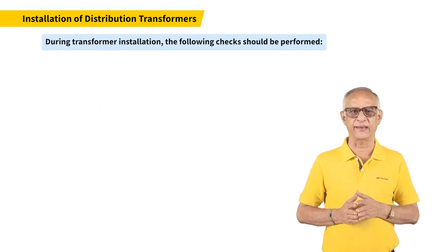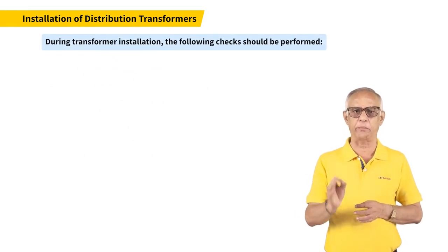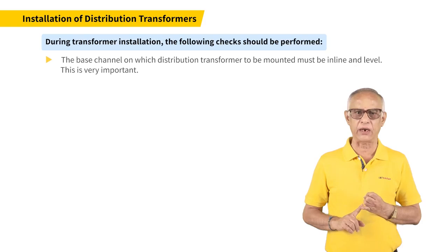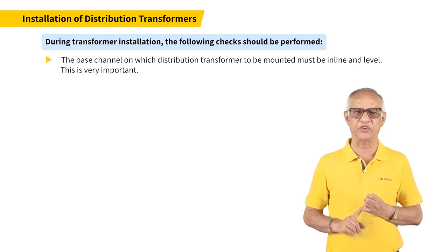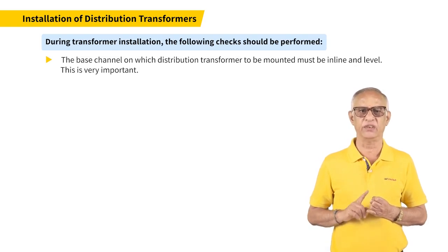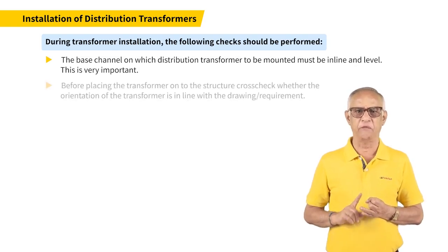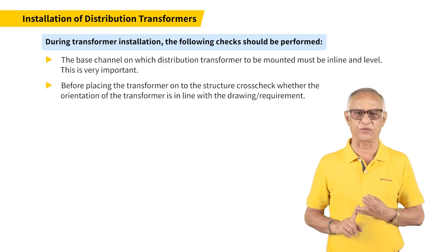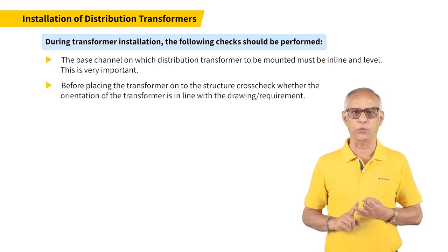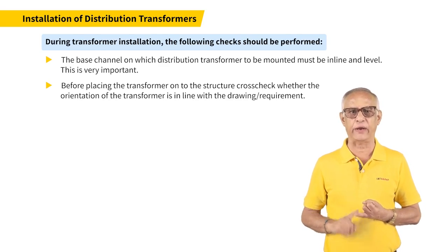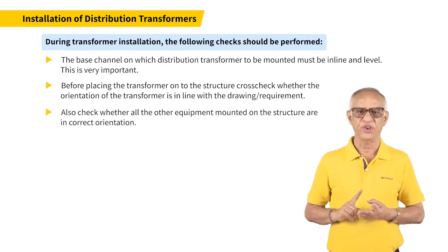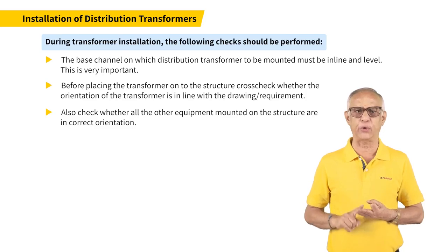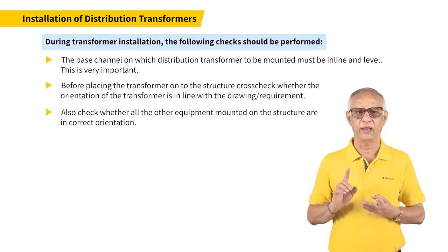During transformer installation, the following checks should be performed. The base channel on which the distribution transformer is to be mounted must be in line and level. This is very important. Before placing the transformer onto the structure, cross-check whether the orientation of the transformer is in line with the drawing or requirement. Also, check whether all the other equipment mounted on the structure is in correct location.